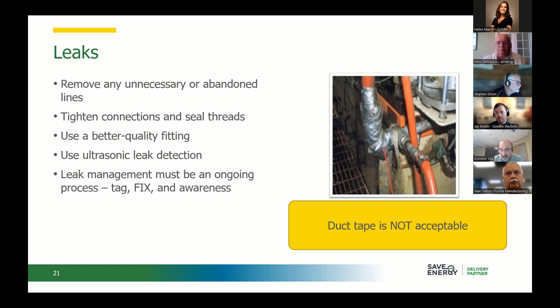One of the things we work with energy managers on a lot is moving to a program, an ongoing basis. Over the course of 6 to 12 months, with reasonable effort at any given time, you're scanning the plant, finding those leaks, repairing them through work orders, but it's an ongoing process. Dominic has mentioned that you fix leaks, but they come back. So it's not a project, it's an ongoing program to minimize that leakage.